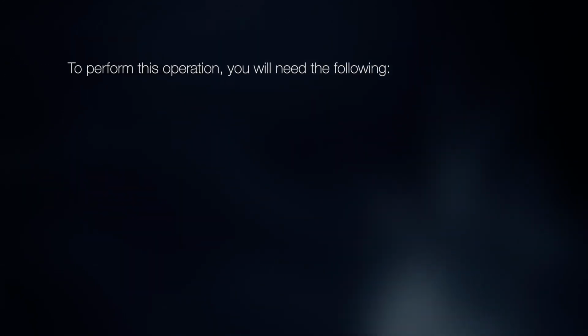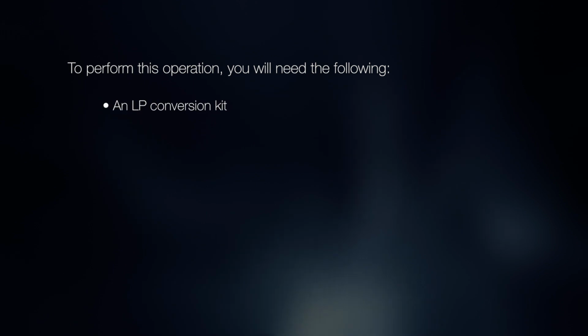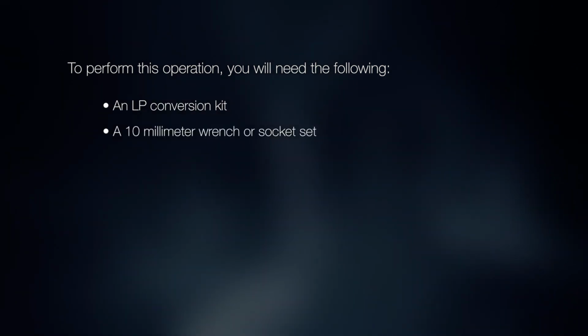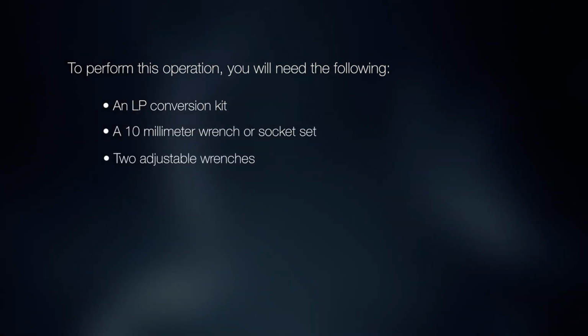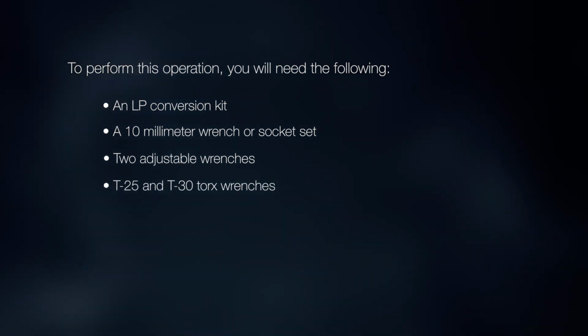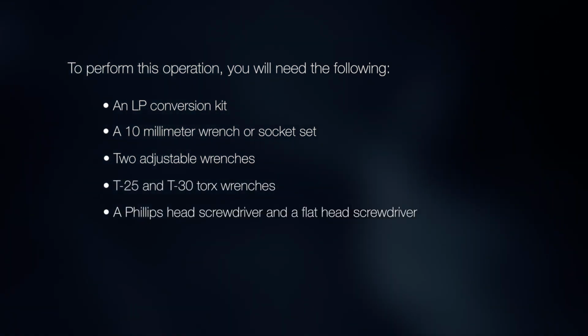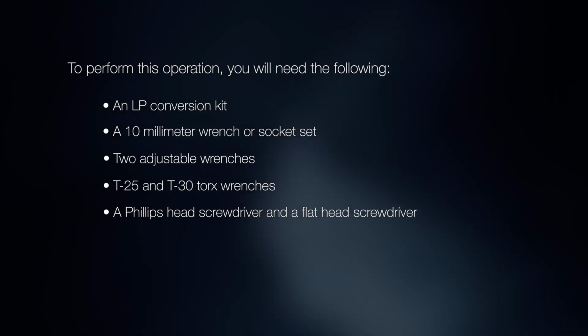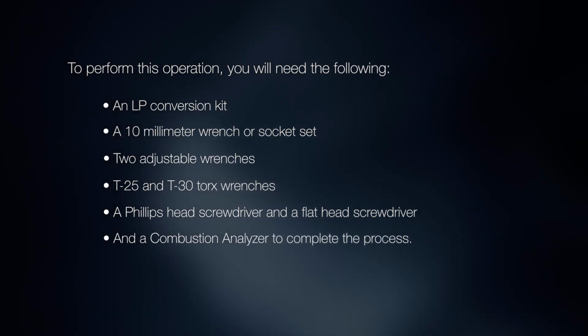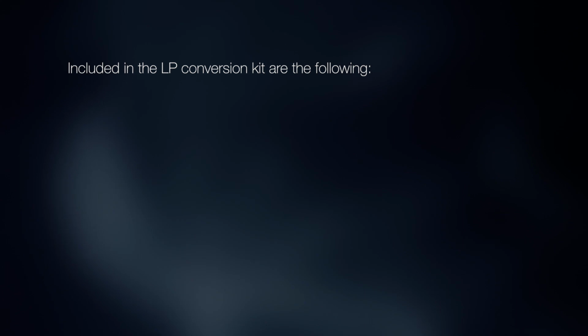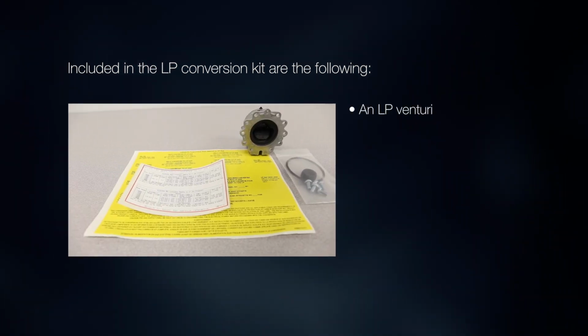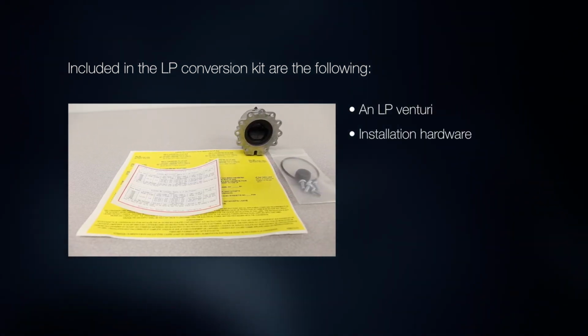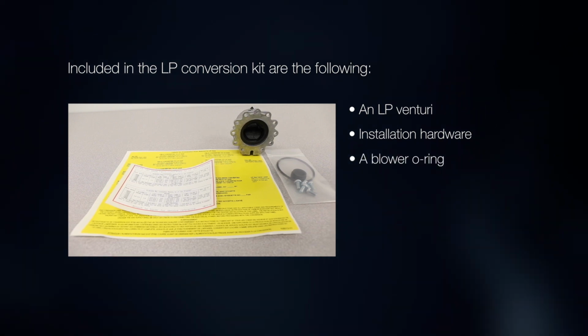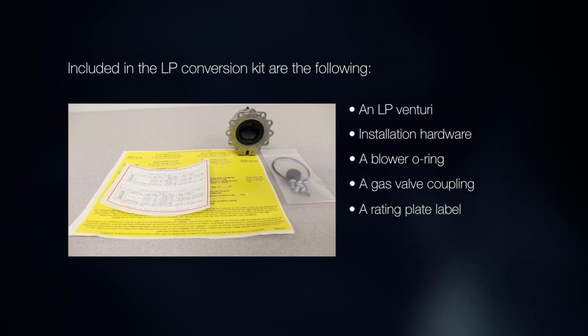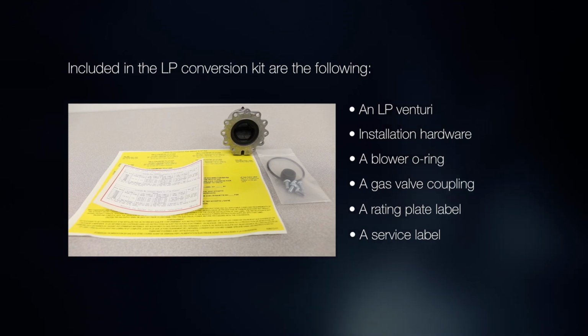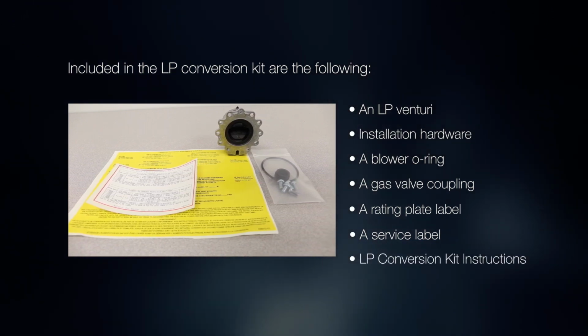To perform this operation, you will need the following: an LP conversion kit, a 10mm wrench or socket set, 2 adjustable wrenches, T25 and T30 Torx wrenches, a Phillips head screwdriver and a flathead screwdriver, and a combustion analyzer to complete the process. Included in the LP conversion kit are the following: an LP venturi, installation hardware, a blower O-ring, a gas valve coupling, a rating plate label, a service label, and printed LP conversion kit instructions.